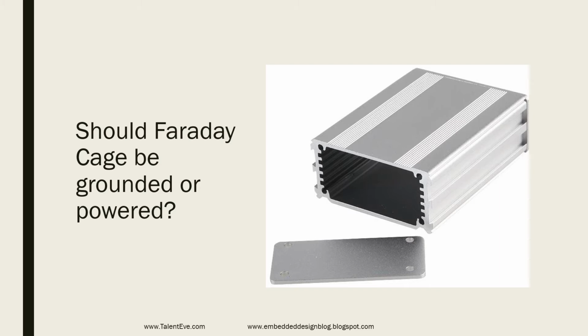Let us assume that we have left it open and have not connected it to an earth terminal. Generally we connect the enclosure to earth, right? In that scenario, where we have just left it open and not connected it anywhere, there will be some static charge present across this enclosure, which causes conductivity, and there might be a chance that this static charge might leak onto your circuit, like how an ESD event can occur.